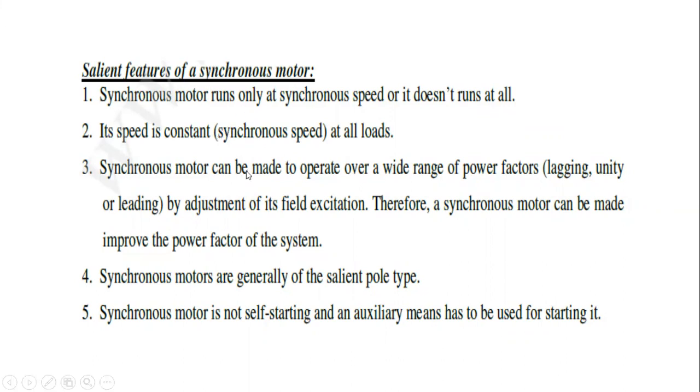The synchronous motor can be made to operate over a wide range of power factors, lagging, unity or leading, by adjusting its field excitation. Therefore, the synchronous motor can be used to improve the power factor of the system.